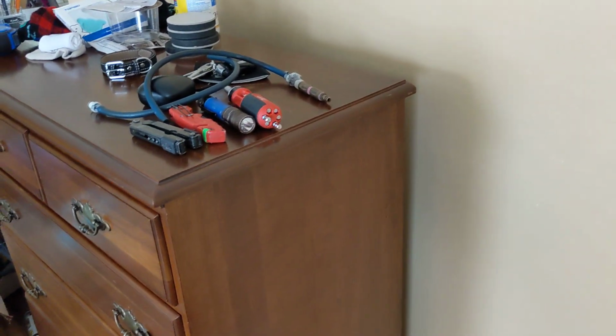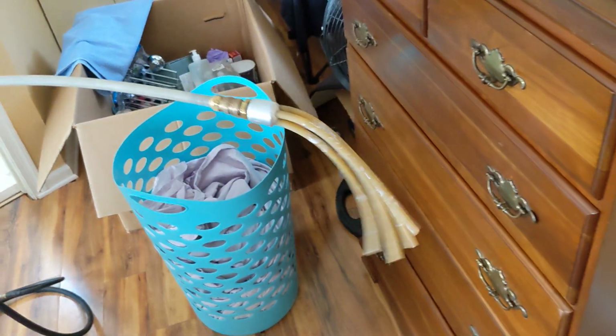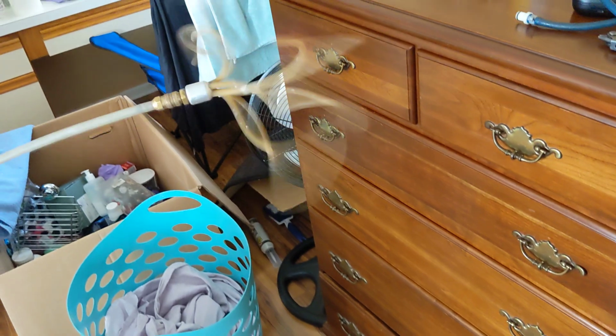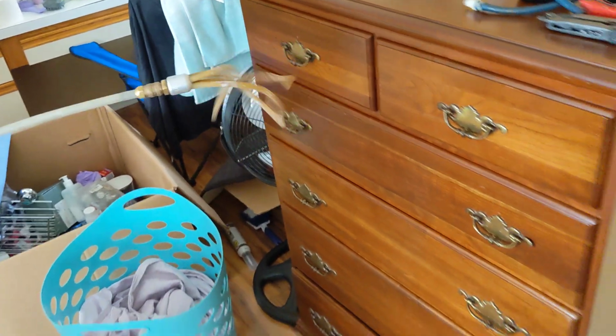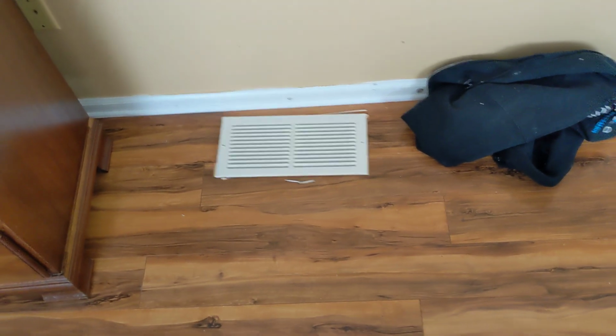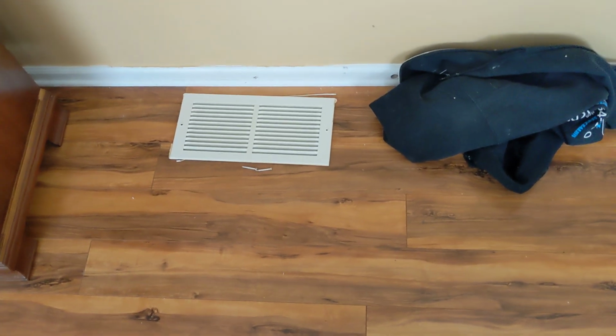And as this whip system is whipping all around, it's knocking all that dust and dirt and debris throughout the system out to the collector. So that's how a whip tip works. So it knocks all the dust and dirt off the system and then blows it towards the collector where it's then collected. So that's about it.